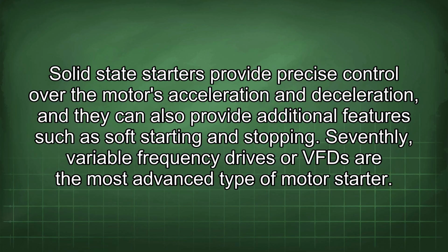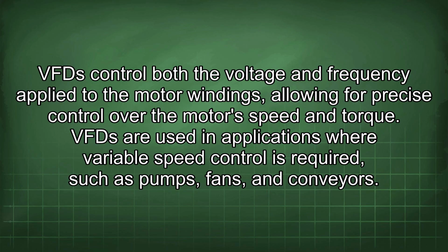Seventhly, variable frequency drives or VFD are the most advanced type of motor starter. VFD control both the voltage and frequency applied to the motor windings, allowing for precise control over the motor's speed and torque. VFD are used in applications where variable speed control is required, such as pumps, fans, and conveyors.